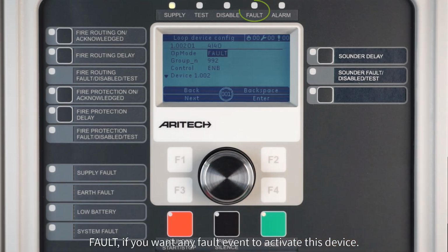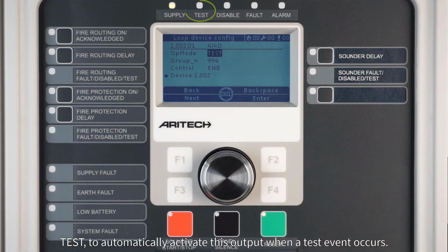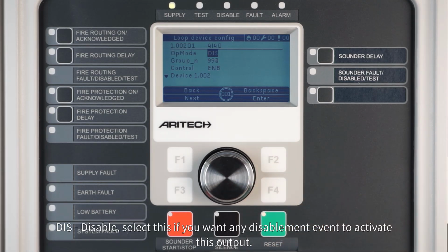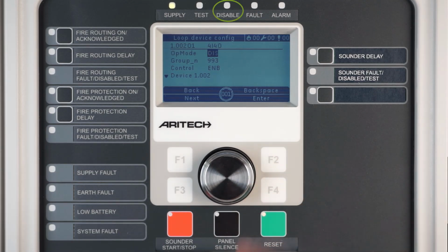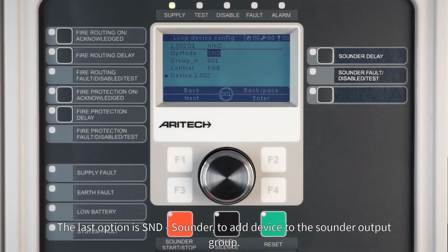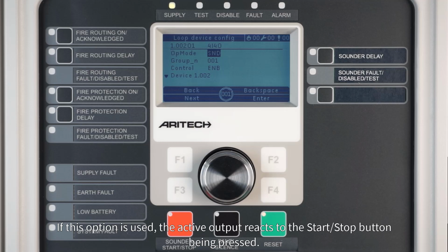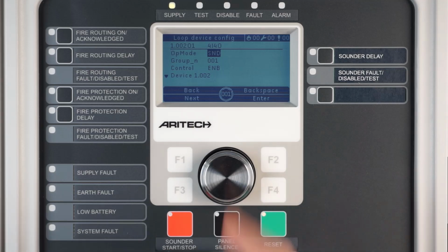Fault, if you want any fault event to activate this device. Test, to automatically activate this output when a test event occurs. Disable, select this if you want any disablement event to activate this output. The last option is sounder, to add the device to the sounder output group. If this option is used, the active output reacts to the start-stop button being pressed.